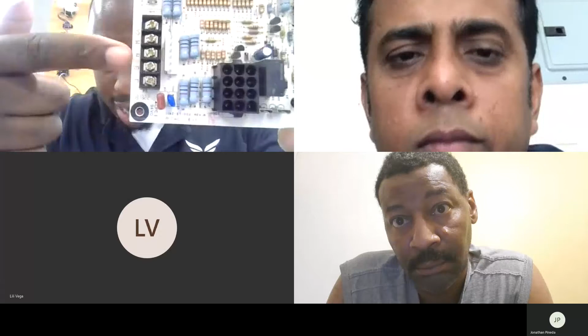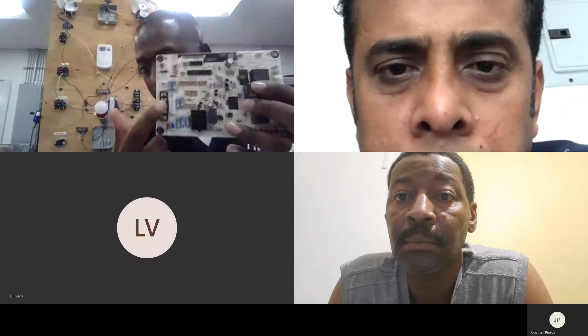But anyway, inside of that furnace, right behind where the blower motor is that I was trying to point out, you guys probably saw this little circuit board. So the terminals — R, Y, G, W, all those things — are right here on this terminal strip down the side. You can kind of see the letters right there, Y, G, and all the different letters. This is located inside of the furnace, so whatever you have connected here, that same orientation has to be at your thermostat. Because in real life, you're not going to have a little strip right here, right below the thermostat. This right here represents this right here.